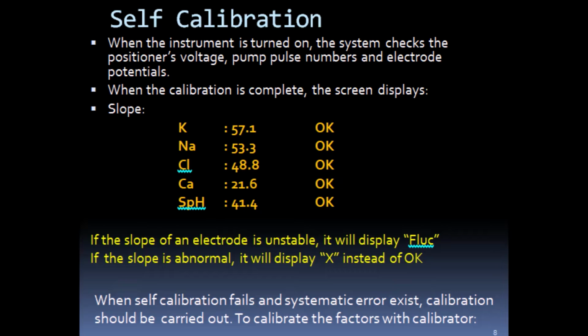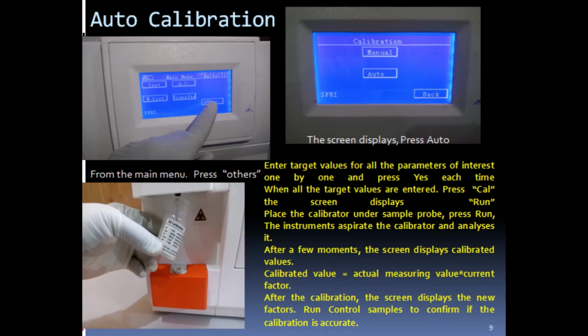When self-calibration fails and systematic error exists, calibration is carried out either manually or automatically. To carry out auto-calibration, from the main menu, press Others. The screen will display calibration with the options of manual or auto. Press Auto. Then enter target values for all the parameters of interest one by one and press Yes each time the values are entered. When all the target values are entered, press Cal. The screen will display Run. Then place the calibrator under the sample probe and press Run.